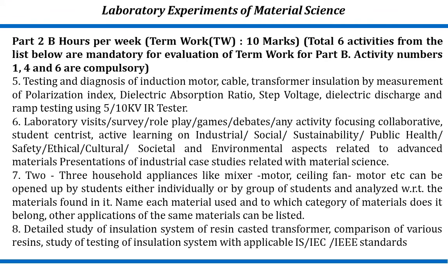Next experiment is testing and diagnosis of induction motor, cable, transformer insulation by measurement of polarization index, dielectric absorption ratio, step voltage, dielectric discharge and ramp testing using a 5 or 10 kV IR tester.